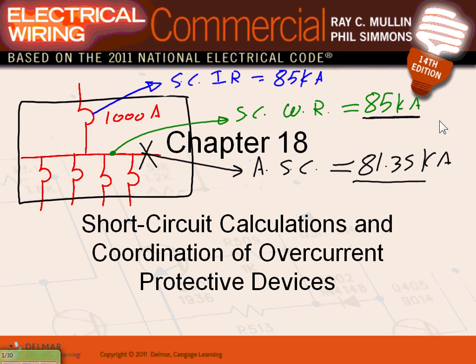So usually the green and the blue values most of the time are the same unless you have current limiting fuses. If you have current limiting fuses or circuit breaker, then this could be 85 and the withstand rating of this could be 70. Why? Well, in this case it can't be 70 because of the short circuit. This could be 83 because the short circuit is 81.